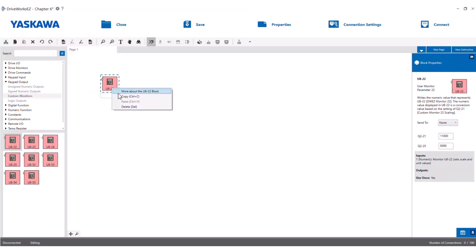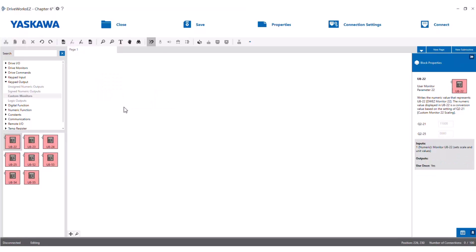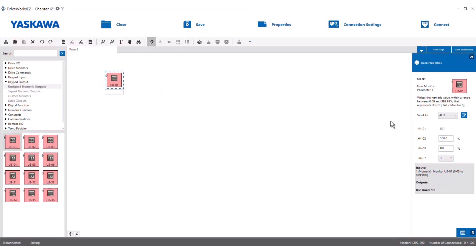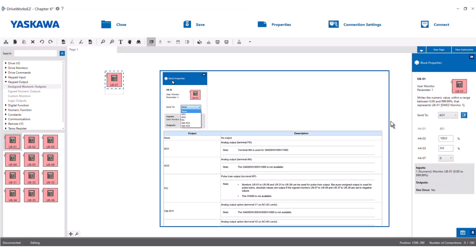There is a secondary purpose to the keypad output blocks that is somewhat hidden. If you are using a GA500 drive, you can use any of the U8 blocks to send whatever signal is incoming to the block to also be sent out the AM analog output of the drive. This is done easily by using the send to drop-down box in the properties window of the keypad output block. This means the value being input into U8-01 could then be output physically from the AM terminals of the drive. This could also be done for the PO or pulse train output — normally the MP terminal. If you have an analog option card for additional analog outputs, you could also send a keypad output to the OPTA01 block, for instance.